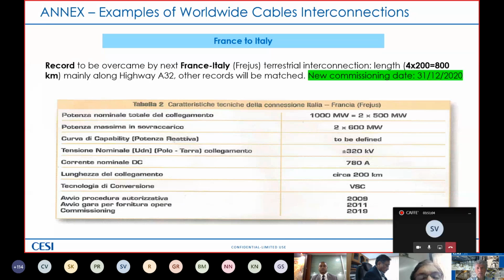But this land interconnection will be overtaken by a new record: the France to Italy terrestrial interconnection. This will have four cables of 200 kilometers each, so the total will be 800 kilometers. This will be commissioned at the end of this year. 2 times 600 megawatt, so 1,000 as nominal, 1,200 as overload.